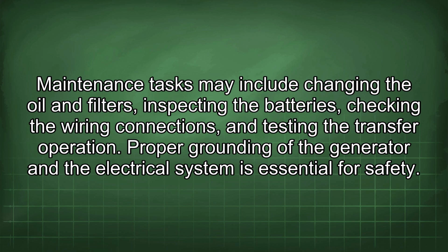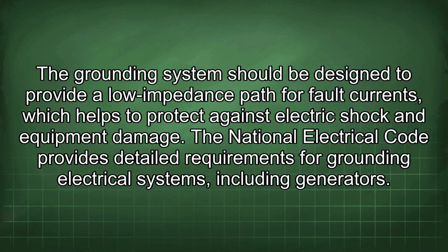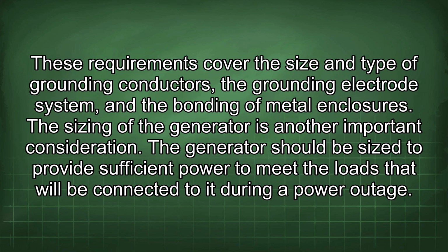Proper grounding of the generator and the electrical system is essential for safety. The grounding system should be designed to provide a low impedance path for fault currents, which helps to protect against electric shock and equipment damage. The National Electrical Code provides detailed requirements for grounding electrical systems, including generators. These requirements cover the size and type of grounding conductors, the grounding electrode system, and the bonding of metal enclosures.